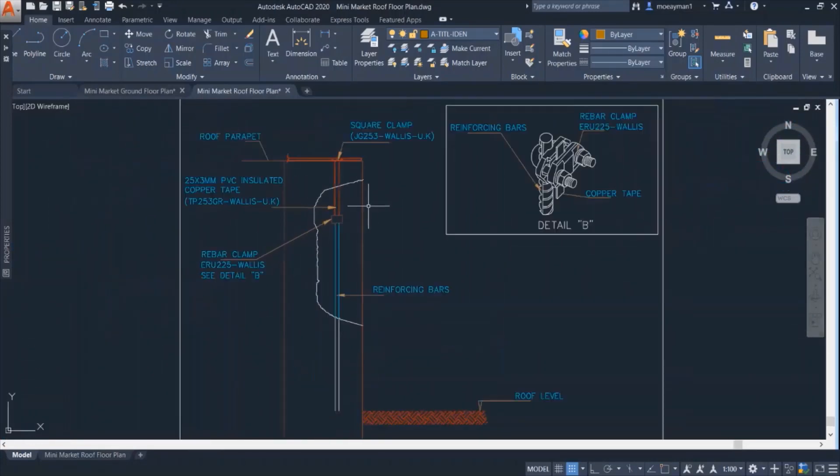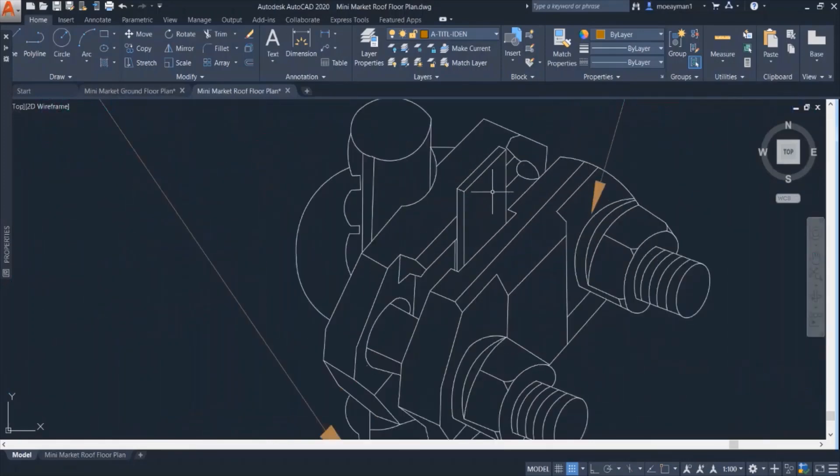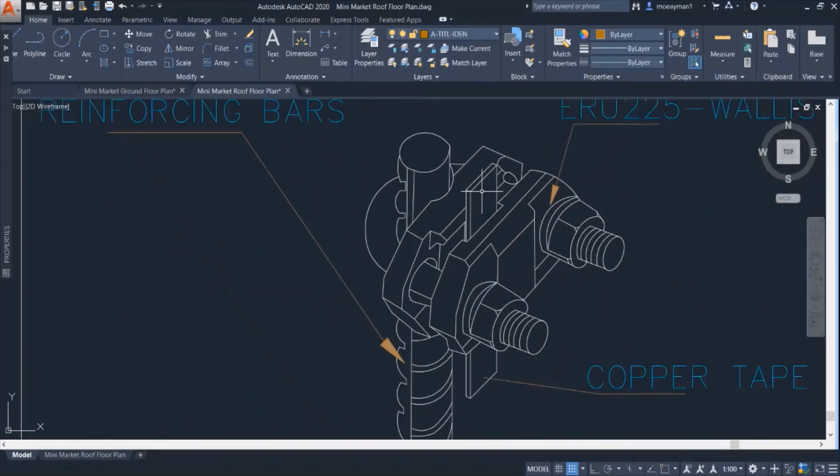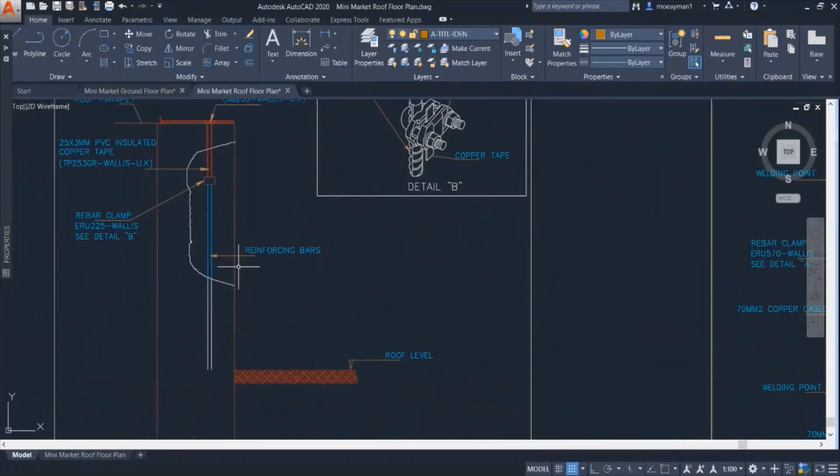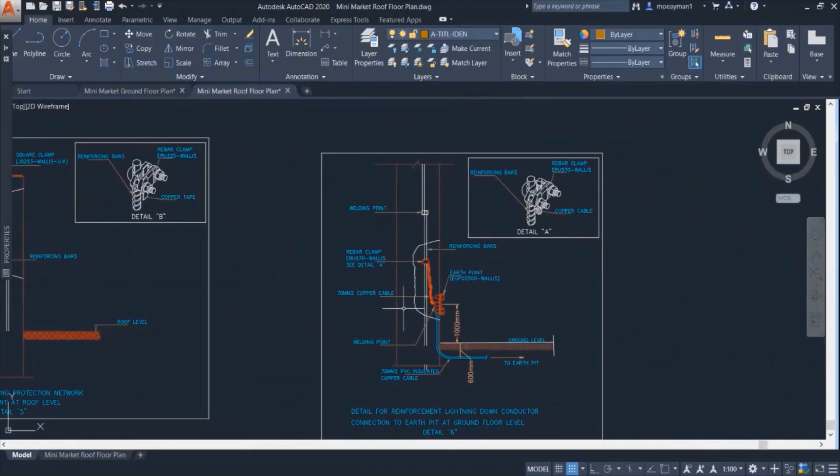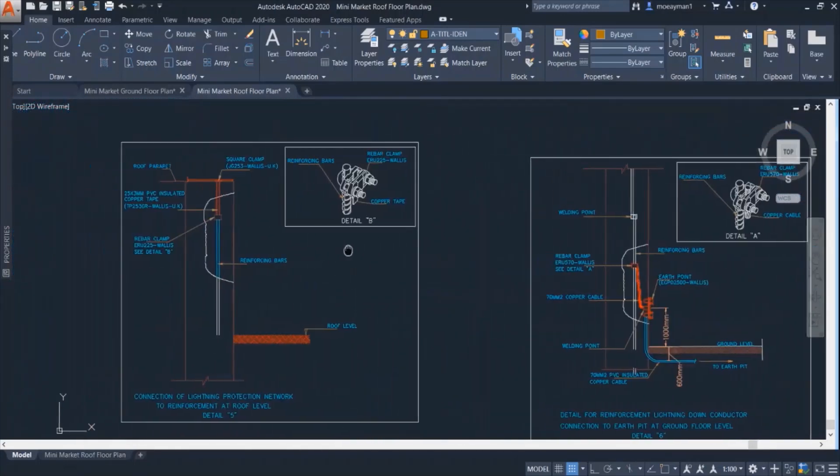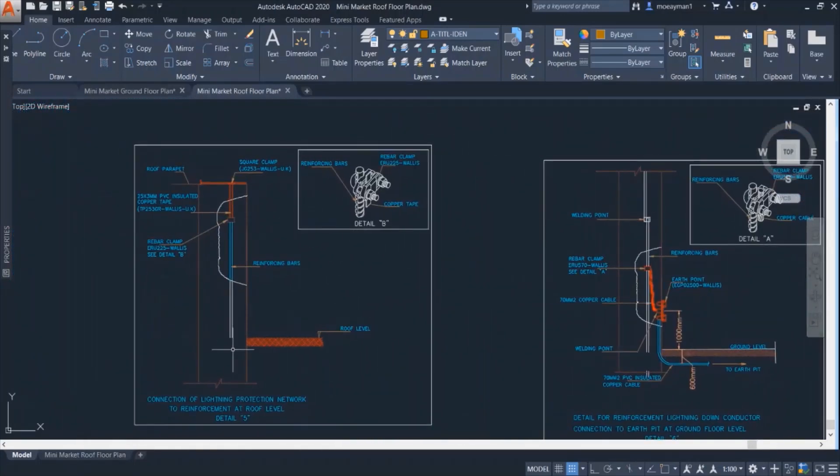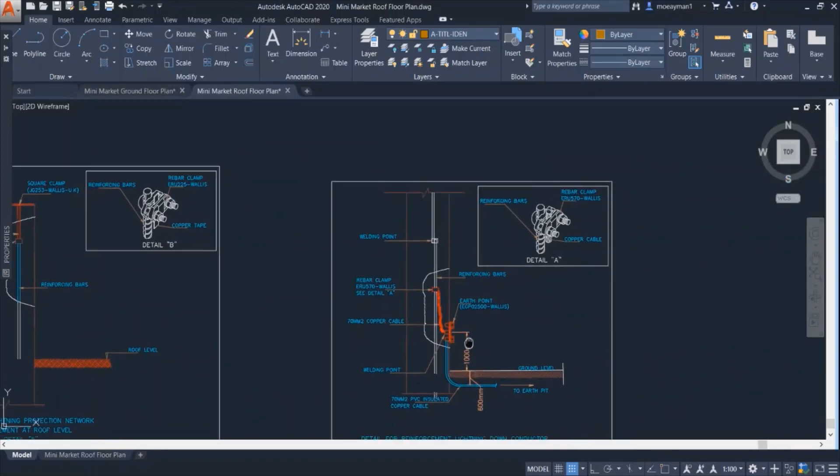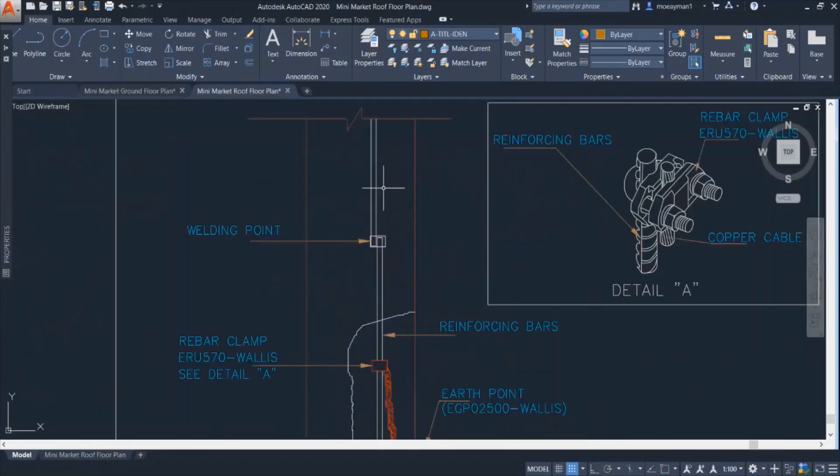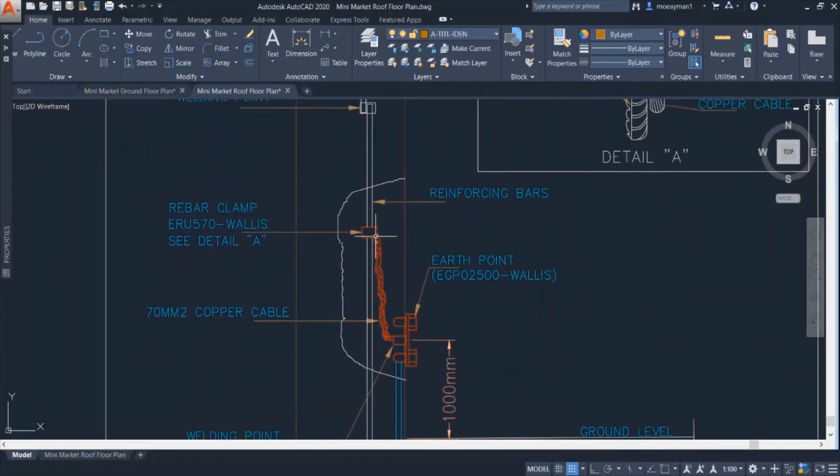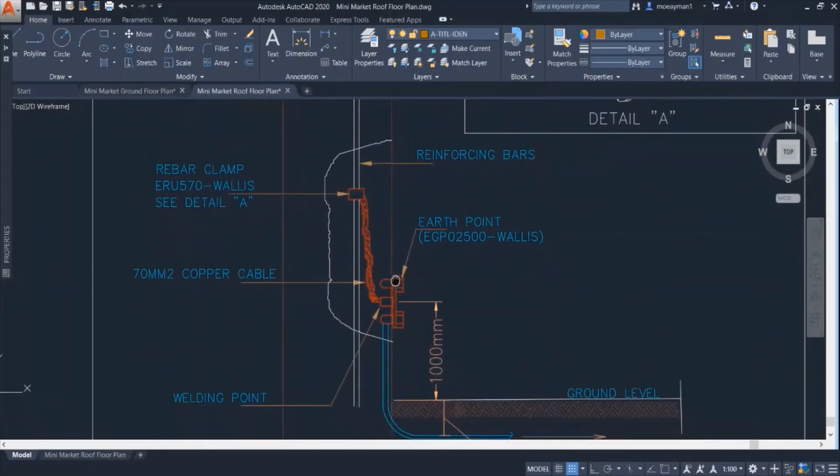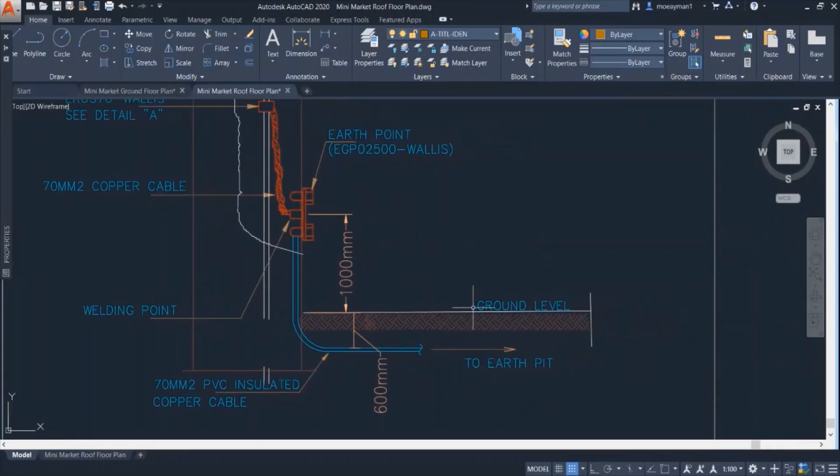So this connection, we can see it exactly how this is how it looks like. The copper tape is placed and also it is saddled into the reinforcing bar. And this is the roof level. We can see that it's taken down to the earth. So this is the top view of this copper tapes. Then this is the bottom view, which is at the floor or the ground level. So we can see the copper tapes are taken down. Then we have here a cable taken from the copper tapes that is taken also down to the earth pit.